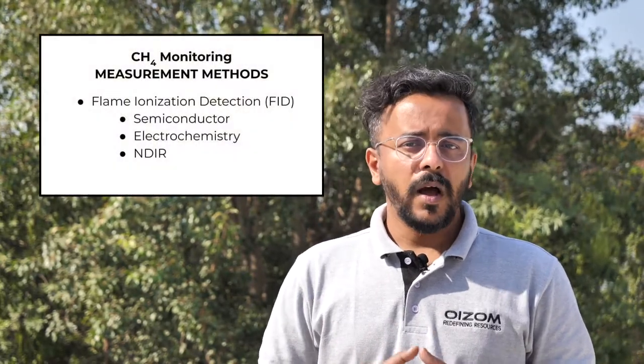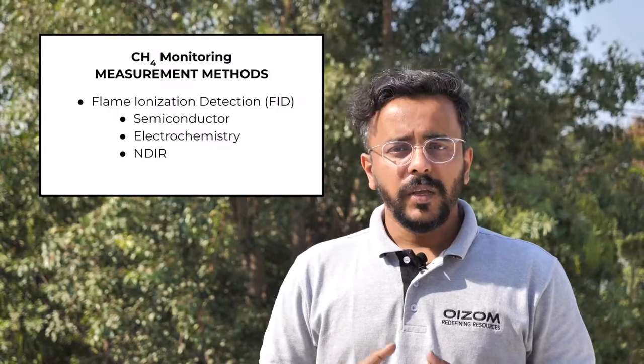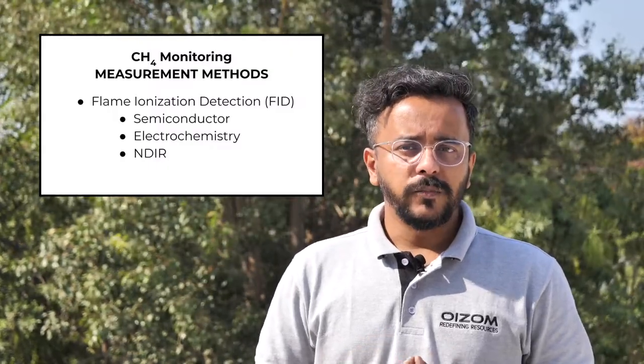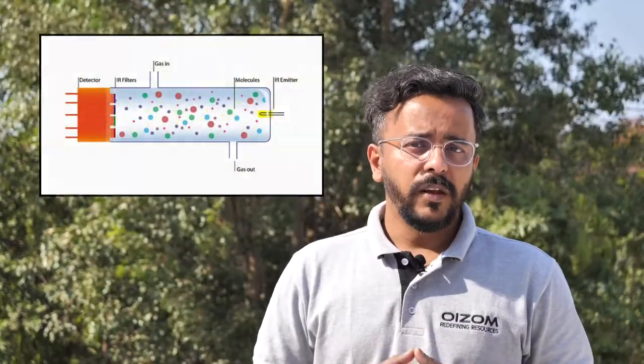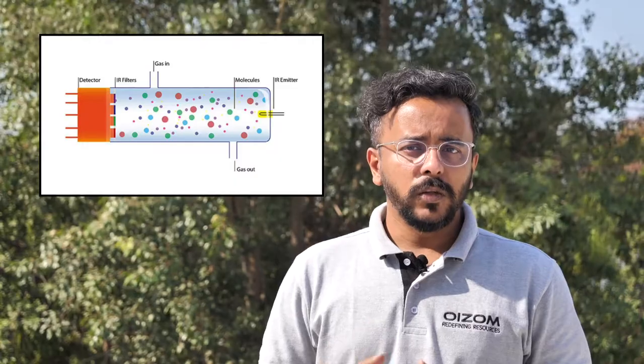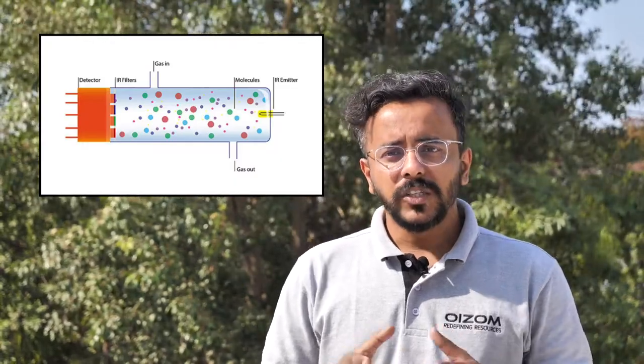Methane monitoring is an efficient way to detect the buildup of methane levels and take necessary actions. Different working principles for methane monitoring in the ambient environment are flame ionization detection, semiconductor, electrochemistry and non-dispersive infrared absorption. At Oizom, our methane sensor works on the principle of NDIR, where the infrared radiation of a specific frequency is absorbed by the methane molecules present in the gas sample and measured by the detector.